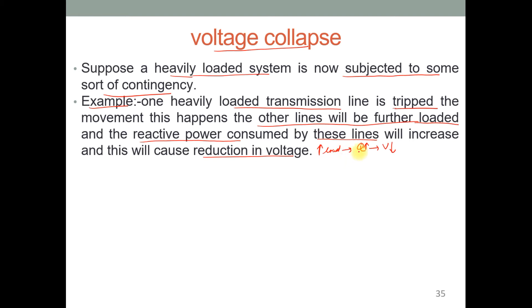Clear? So the same things will happen over here. If the heavily loaded transmission line is tripped from the system, then the load which is transferred by that transmission line is transferred to the other transmission lines which are already loaded. So these transmission lines are further loaded, and hence the reactive power consumed by these lines will increase. That will cause the reduction in voltage as the reactive power is increased.